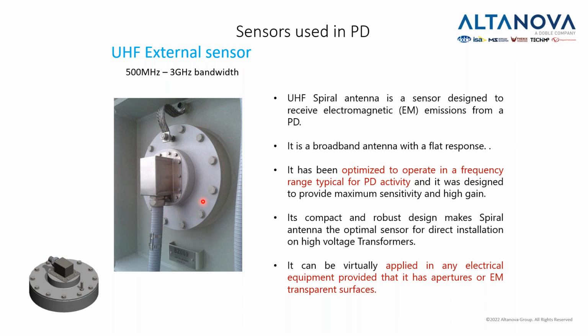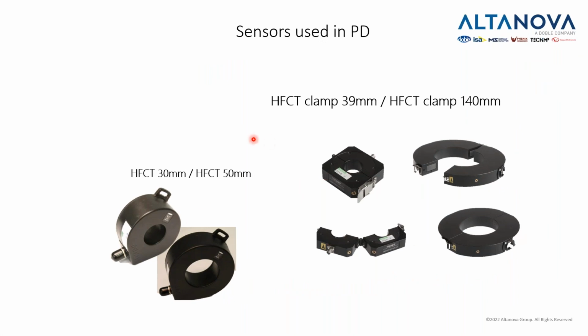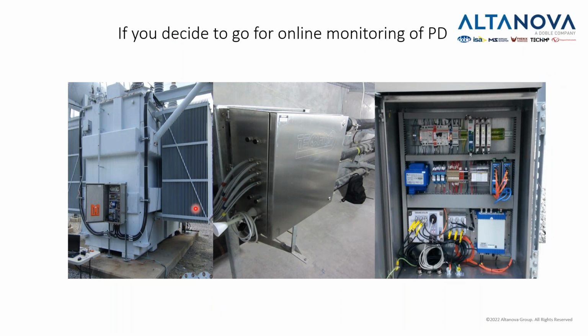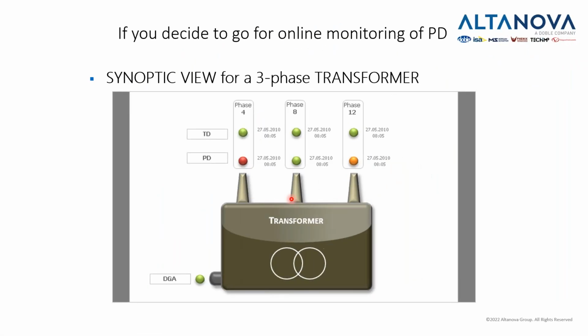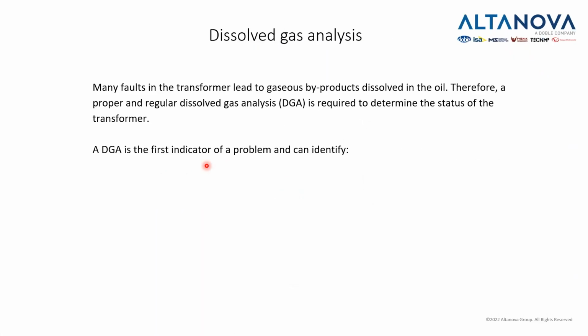This one will be used if your transformer has a window, and these ones will be used on the grounding leads of your transformers if you cannot connect your tap adapter sensors. If you decide to go for online monitoring, then the whole system will contain a box like this, which will contain an acquisition unit and which will monitor your transformer 24/7. And it will show it to you like this in your SCADA system if your bushings and your transformer have problems with tan delta or partial discharge.